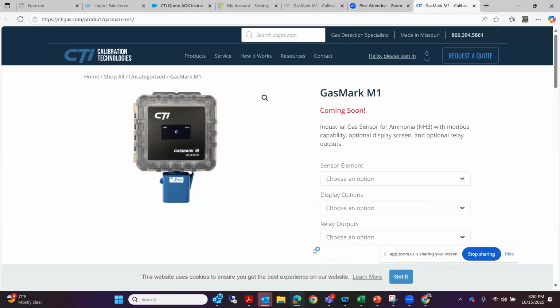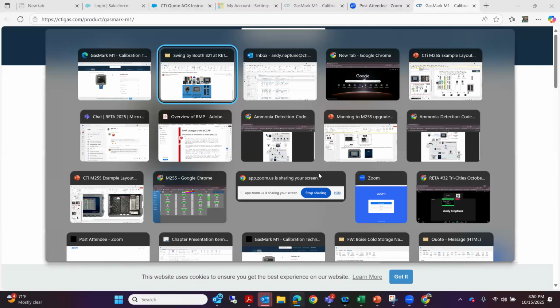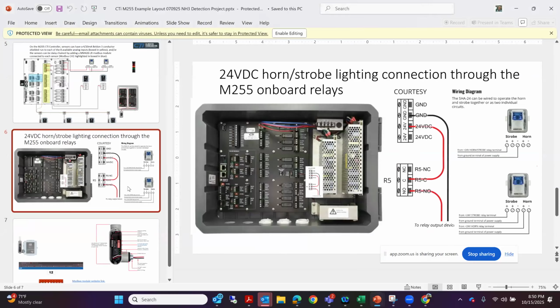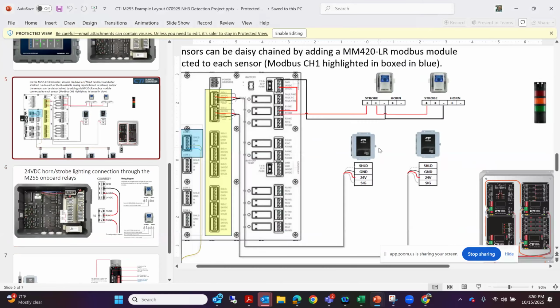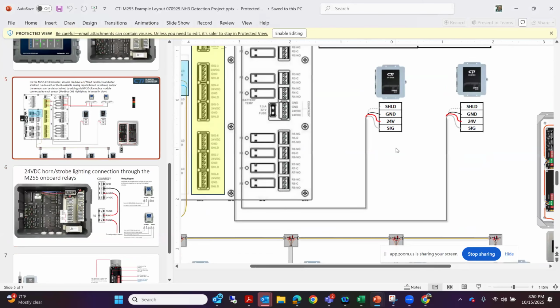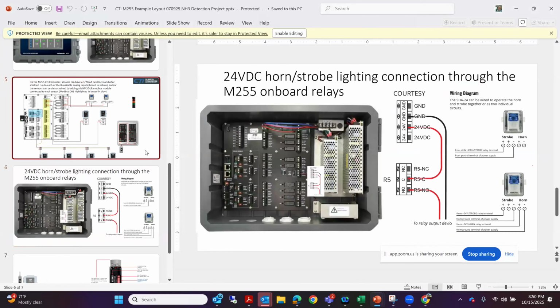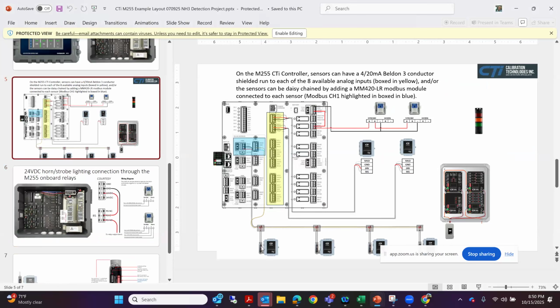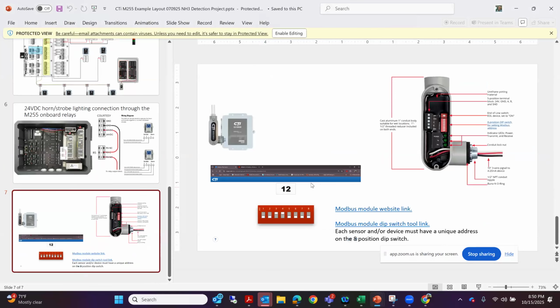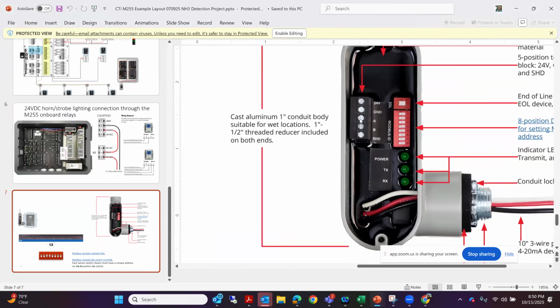So this is CTI's new M1 sensor. What you guys are used to seeing is probably the legacy stuff. We didn't want to leave anybody behind on this Modbus system, so we developed this module. You can see the sensor is connected to this. It takes the 4-to-20 sensor output into this Modbus module and converts it, allowing it to go onto that Modbus chain on the A and B Modbus comms. Then you just power and ground it, and assign the dip switch an address.